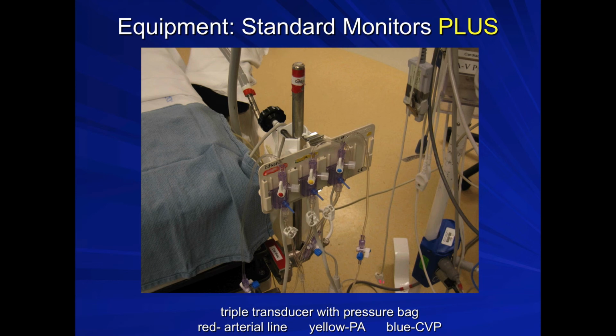The equipment in a cardiac OR includes standard ASA monitors plus the following devices: triple transducer with pressure bag, with red transducer corresponding to arterial line, yellow transducer corresponding to PA catheter, and blue one to CVP monitoring.